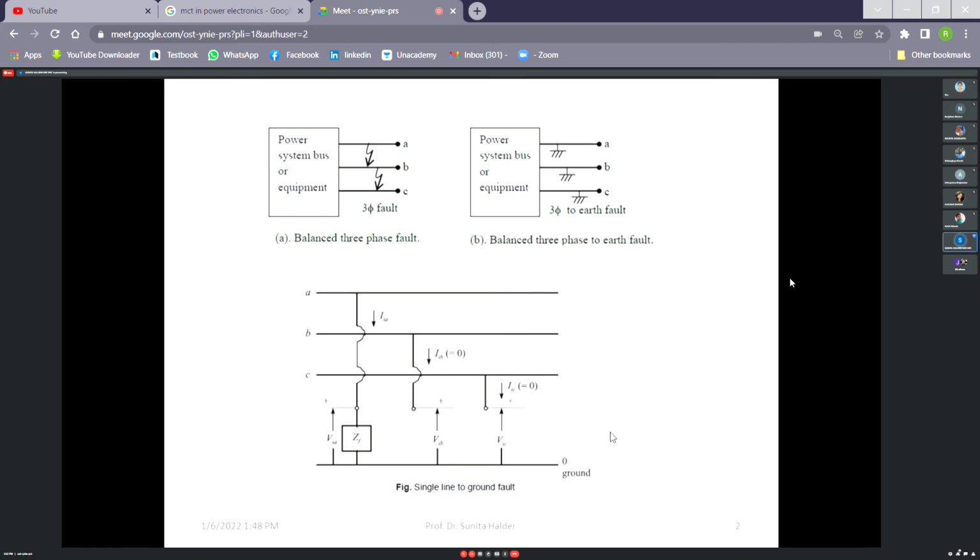We have to identify if there is any abnormality in current in the system, because short circuit means high current will flow. Normally in a power system, on a long transmission line, near 400 to 500 ampere current is very normal. But generally, in per unit, 2 to 3 per unit current is flowing. So 1 per unit is 400 means 3 per unit is 1200 ampere current flowing. So we have to disconnect that faulty portion at first from the healthy portion. Then we shall identify the fault point, repair the faulty part and connect it again to the healthy part.